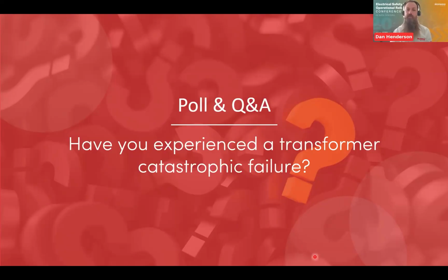That's good. Good that a lot of people haven't experienced it. To those that have, hopefully there was no one in the vicinity, because obviously a catastrophic failure of a transformer can have massive consequences from a safety perspective. If no one was in the vicinity, again, there's the near miss potential that someone could be in, but probably the biggest one that we have experienced, those of us that have had a transformer failure, is the business impact. It's normally quite a long process to try and identify the root cause, try and get any remediation to get everything back up and running. And often, when it's adjacent to things, it causes prolonged damage to other things in the area, cabling, possibly back to the circuit breaker. So the business impact alone, the downtime, is normally the impact that we take away, providing there's nobody in the vicinity. Obviously, safety is the biggest concern. But it's just understanding what those impacts look like, and I was just trying to gauge whether people had any experience of that.